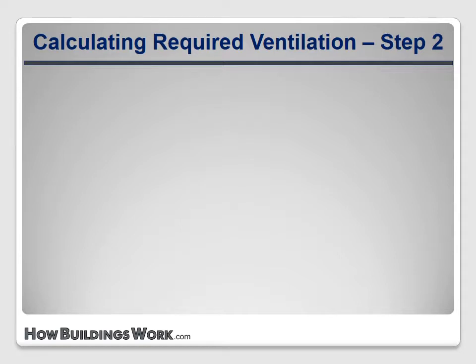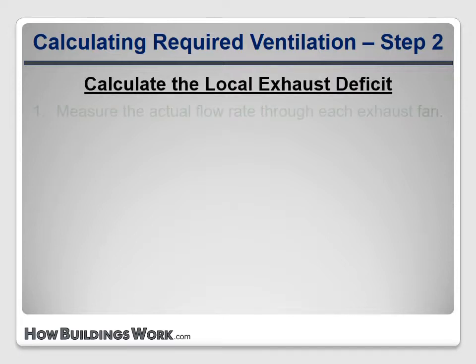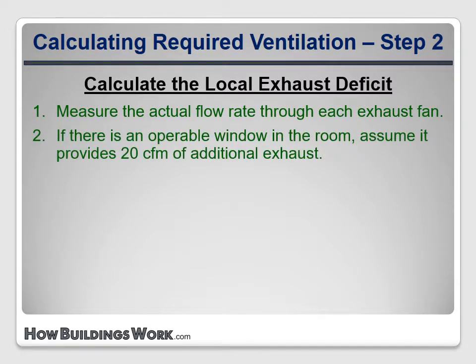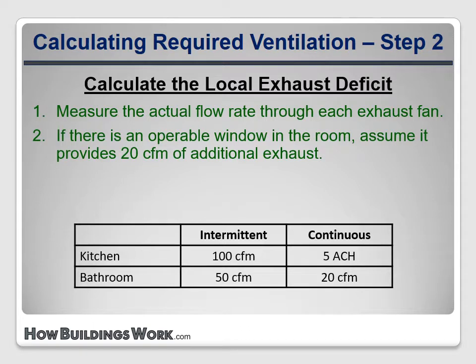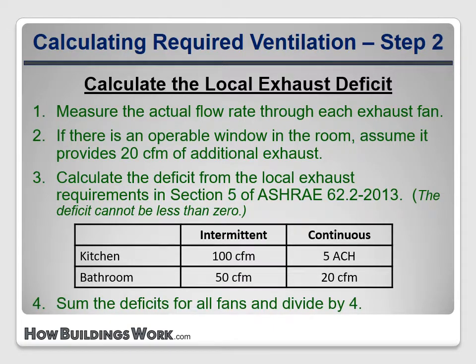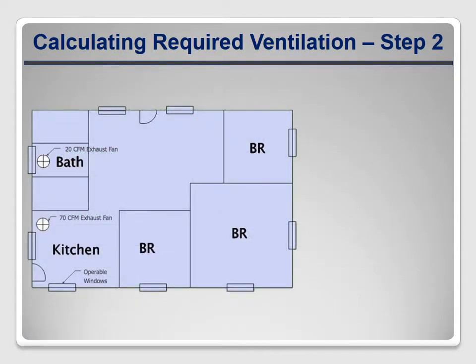But that assumes strong local exhaust rates, which isn't the case in this house, so we'll need to add whole house ventilation to account for this. First, we measured the actual flow rate through each fan. We visually determined that the kitchen and bathroom each had operable windows. Now we can look up the required flow rate for those rooms: both fans are operated intermittently, so the kitchen should be 100 CFM and the bathroom should be 50 CFM. The final step is to sum up all the deficits and divide by four.